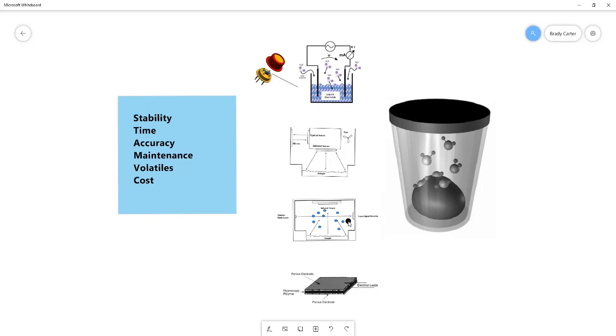The presence of other volatiles does not cause problems. The electrical properties, the capacitance polymer sensor is the next in terms of its sensitivity to volatiles, because it can actually read with the presence of volatiles fairly well. But continued exposure to these volatiles will eventually change the polymer and cause its calibration to be shifted. So even it will be poisoned eventually.